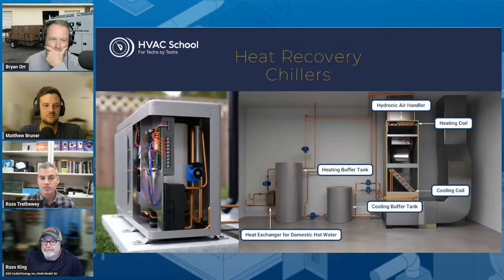So, it gives us the kind of ultimate flexibility. If a house wants radiant floor heat, we can do that with this system. If they want to run dehumidification, we can do that with the system. And hot water, chill water systems are not new, right? Hot water, chill water is a lot of how high-rise construction is built, with a 4-pipe system, hot water off the boiler plant, and chillers that are doing the chill water side of it. So using hydronics is nothing new here. It's much of how Europe is heated, of course.